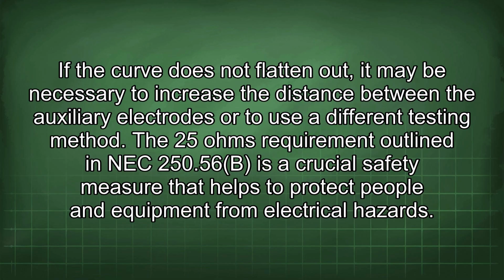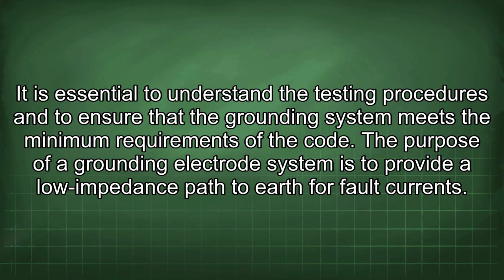The 25 ohms requirement outlined in NEC 250.56(B) is a crucial safety measure that helps to protect people and equipment from electrical hazards. It is essential to understand the testing procedures and to ensure that the grounding system meets the minimum requirements of the code. The purpose of a grounding electrode system is to provide a low impedance path to earth for fault currents.